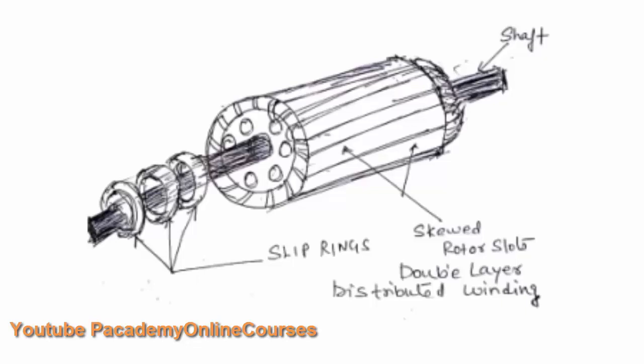The slip rings are connected to external circuit via brush contacts. This will help to introduce resistance in the rotor circuit. The rotor speed is similar to the case of squirrel cage induction motor and the winding here is double distributed winding.